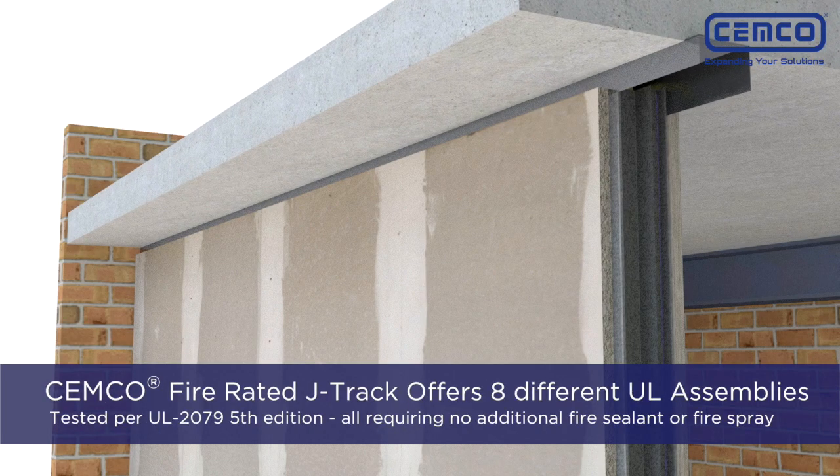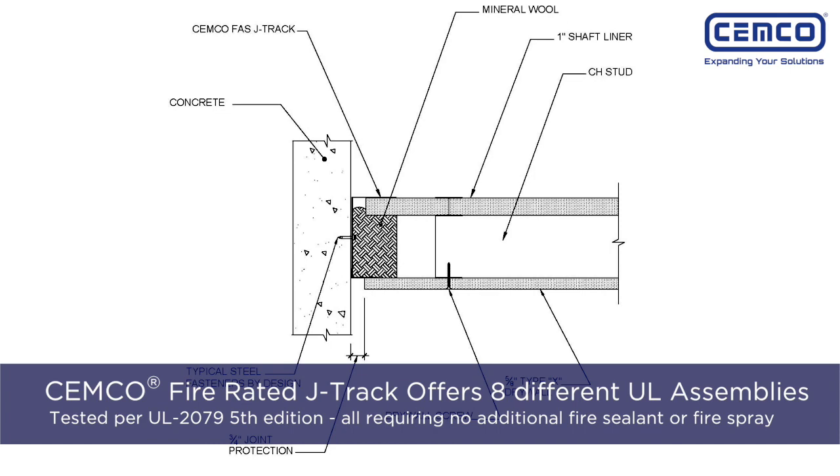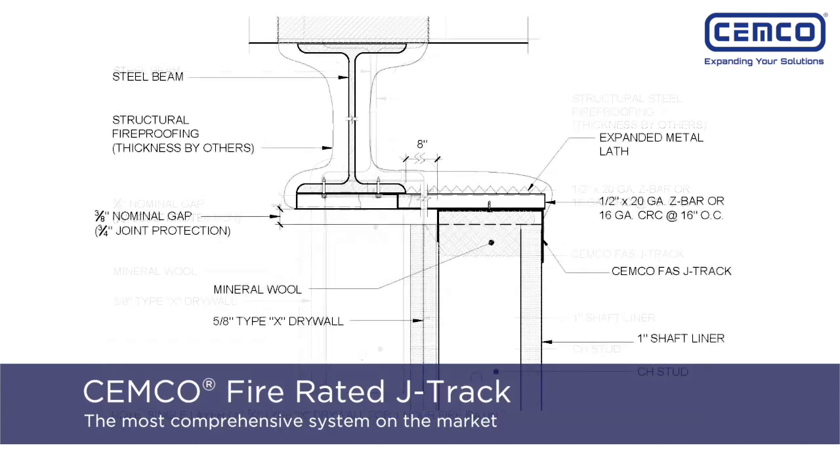The CEMCO Fire Rated J-Track offers eight different UL fire rated assemblies tested per the UL 2079 fifth edition, all of which require no additional fire sealant or fire spray. The CEMCO Fire Rated J-Track can be used with any UL certified shaft liner or UL certified drywall.